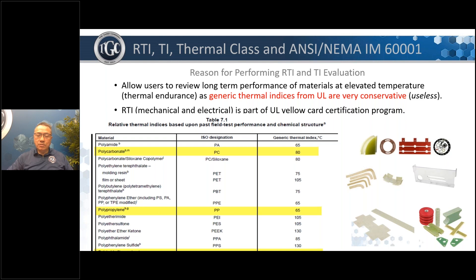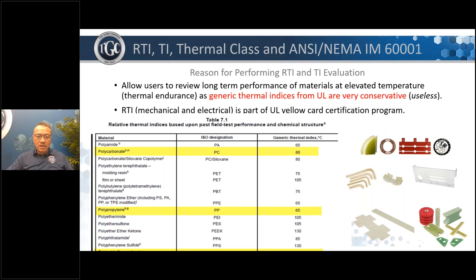You can obtain RTI two ways. If you don't want to spend the money, then UL will give you a generic RTI based on the chemistry of the material. The generic RTI that UL gives out is very conservative — sometimes even useless. If you look at the example below, polypropylene has a generic RTI of 65 degrees C.